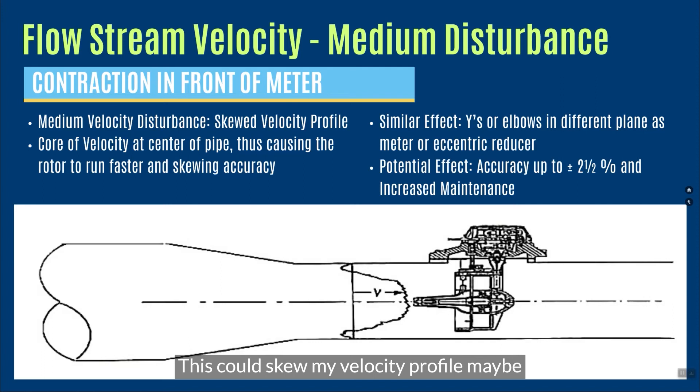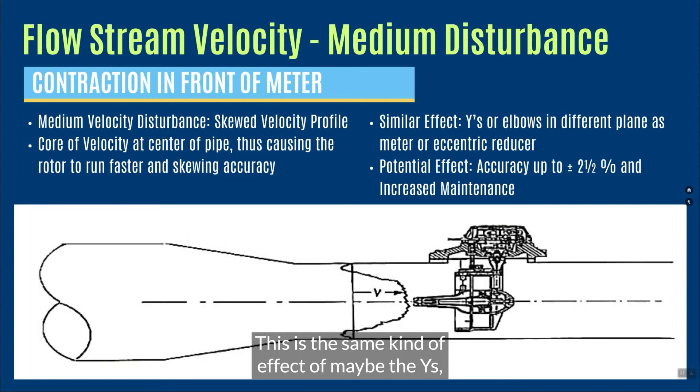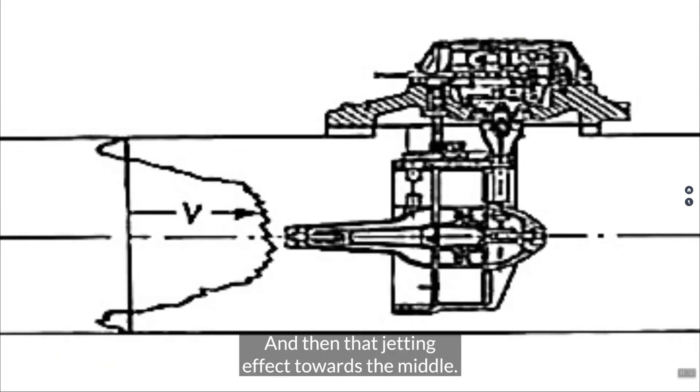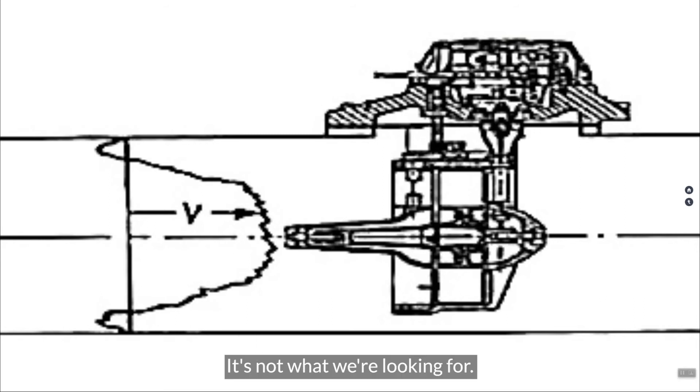This could skew my velocity profile maybe two and a half or three percent, plus or minus. This is the same kind of effect of the maybe the Ys or elbows or, in this case, eccentric reducer. What it's going to do that for that velocity profile here is it's going to give me sort of two eddy currents now towards the top and towards the bottom because of this contraction, and then that jetting effect towards the middle. It's not what we're looking for.